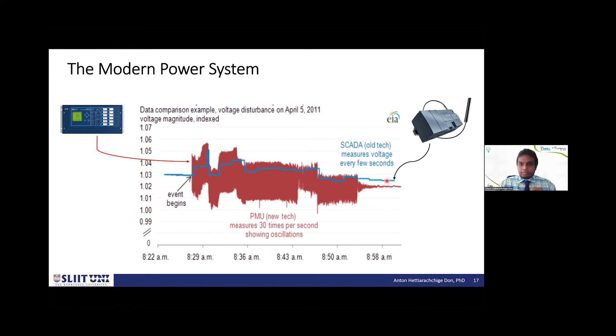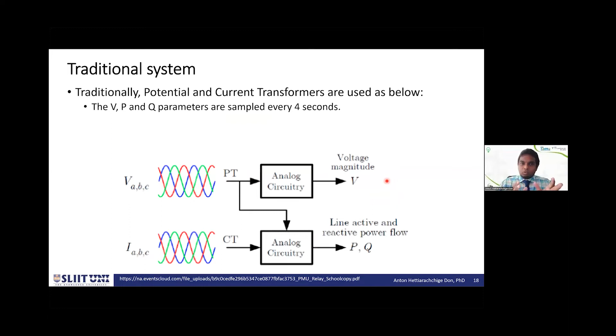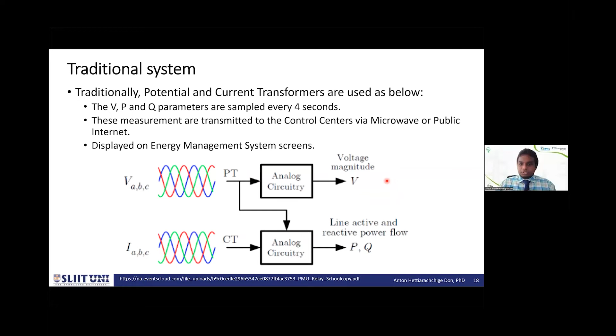The traditional system works like this: you have potential and current transformers at substations that take in voltage, power, and reactive power data about every 4 seconds, older ones even every 10 seconds. Then they send it to control centers via microwave or the public network or whatever method the utility implements, and it shows up on the energy management systems. That is the traditional system. But PMUs are changing this.